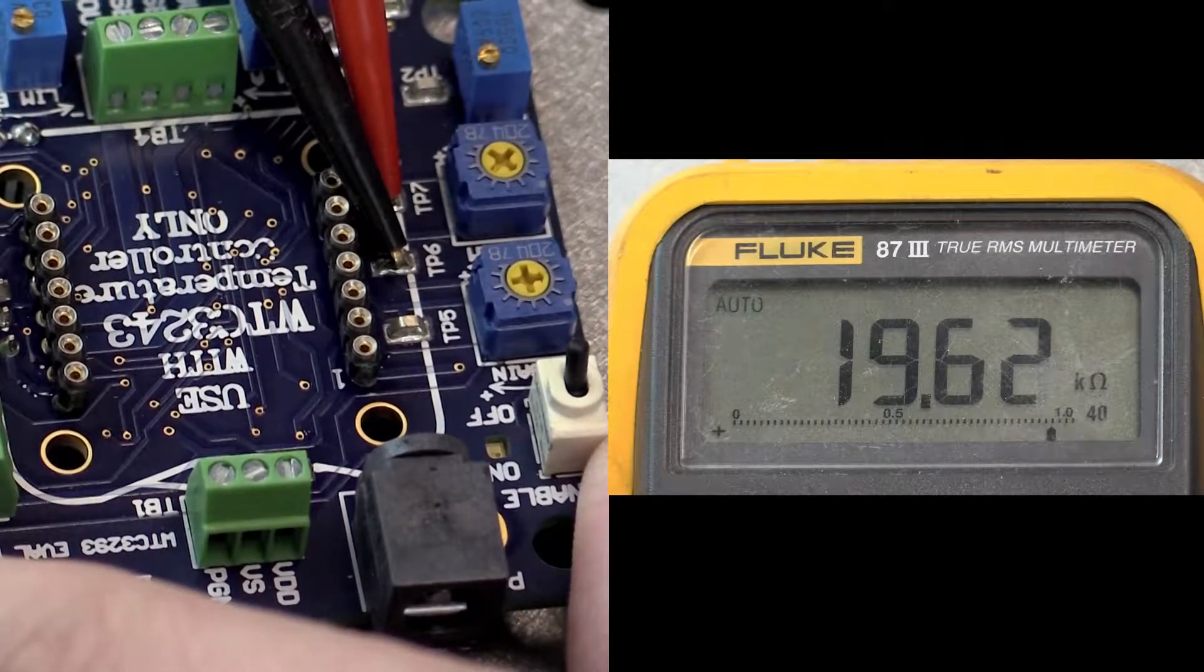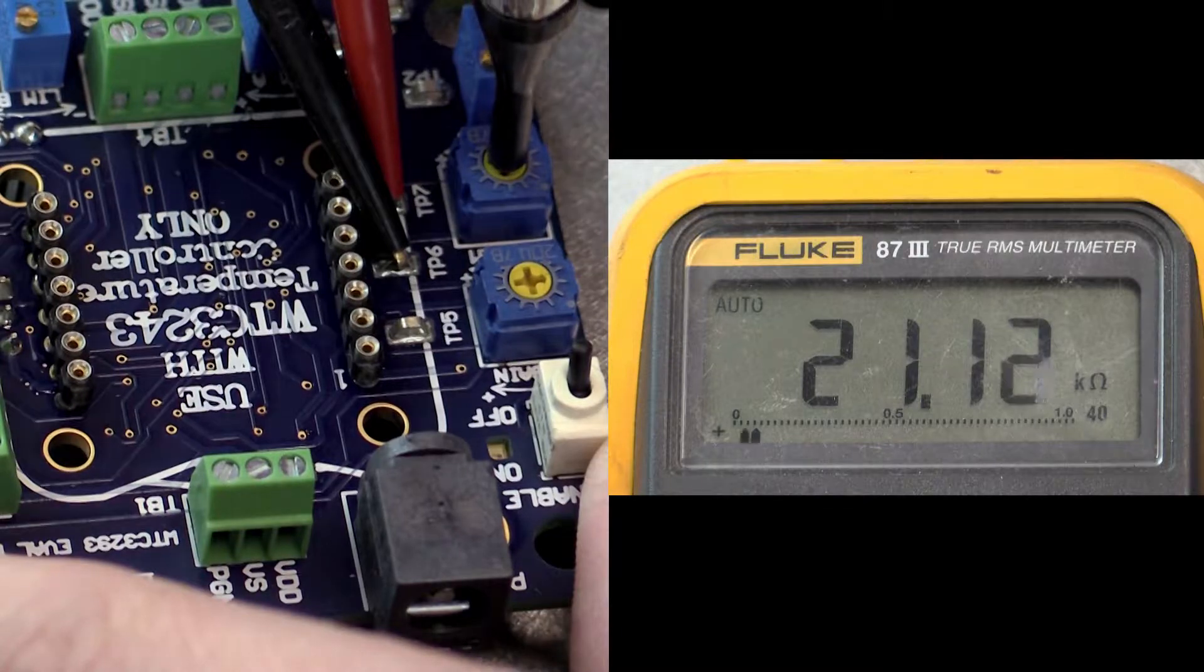To adjust the I-term, use an ohmmeter to measure the resistance between test points TP6 and TP7. Adjust the I-term trim pot to the calculated resistance.